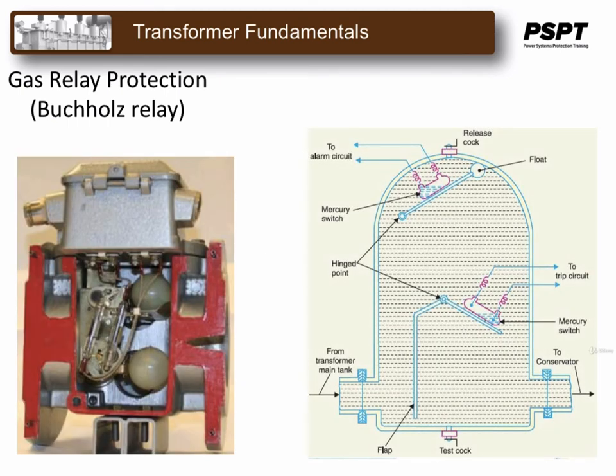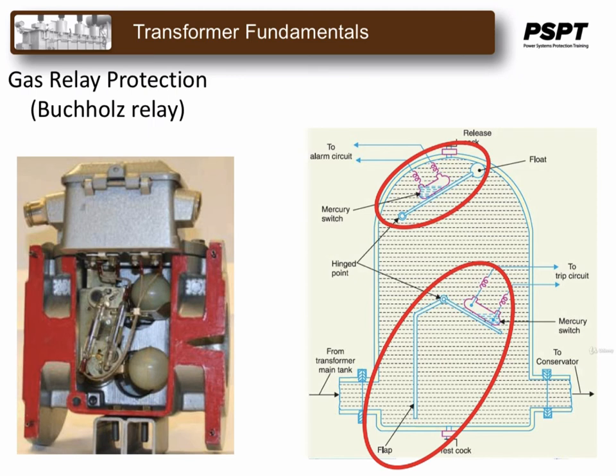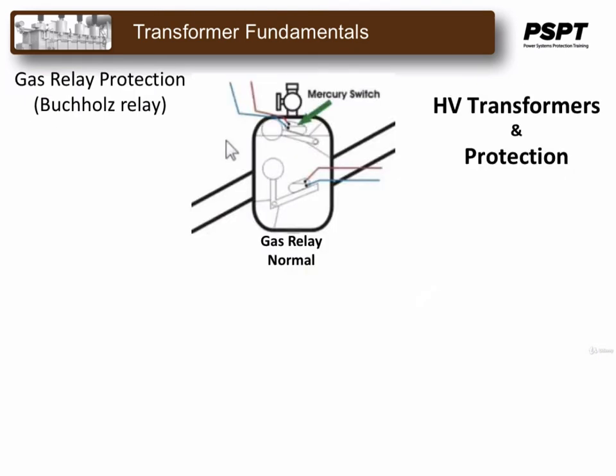The Buchholz relay usually has two elements that monitor, number one, gas accumulation, which is made up of a float and some kind of position activated switch. In this case, it shows a mercury switch, which in the more eco-friendly designs of today can possibly be a reed relay acted upon by a moving magnet. The second element measures gas pressure change, which is made up of a moving diaphragm and again some kind of position activated switch, a mercury switch or the more eco-friendly reed relay. For the time being and for simplicity, let's assume that the mercury switch is being used in both cases.